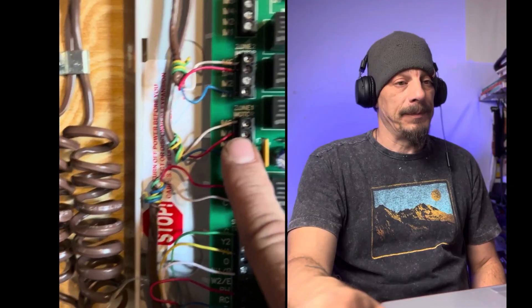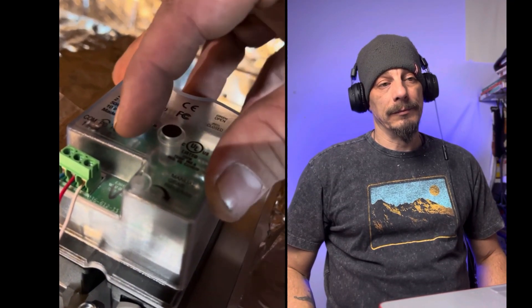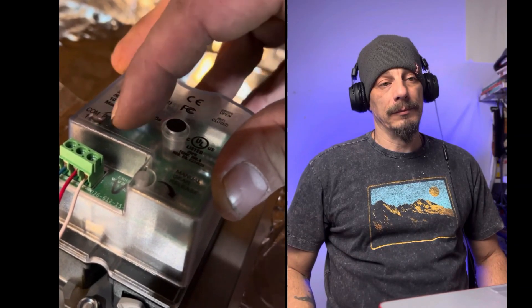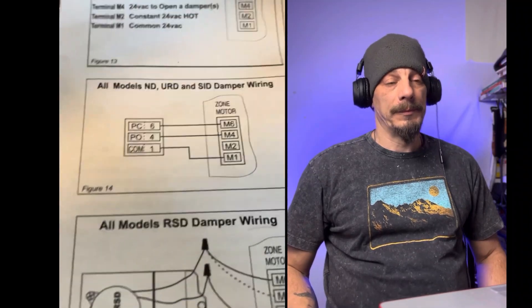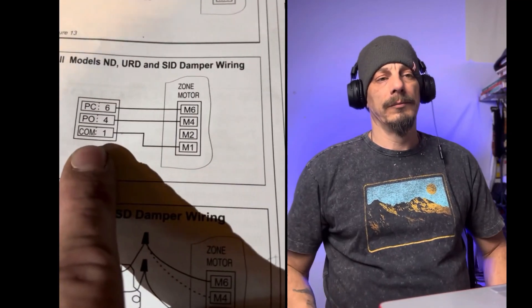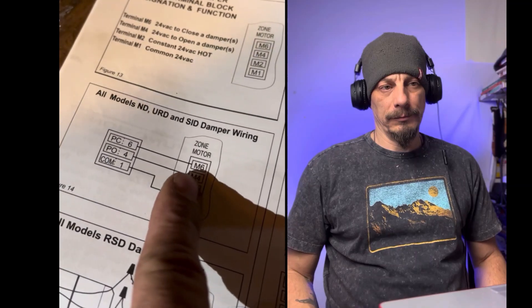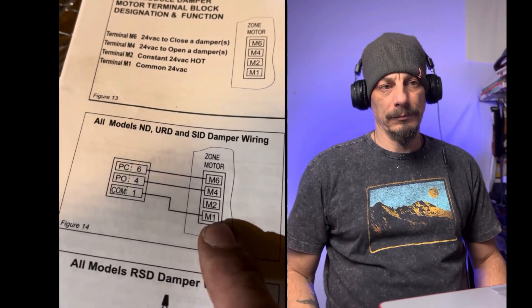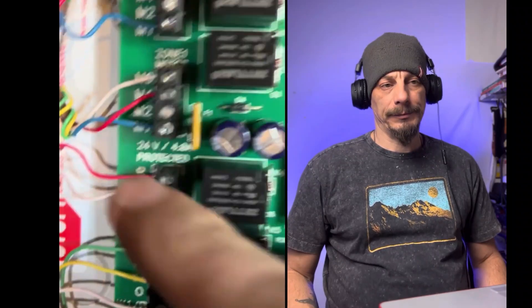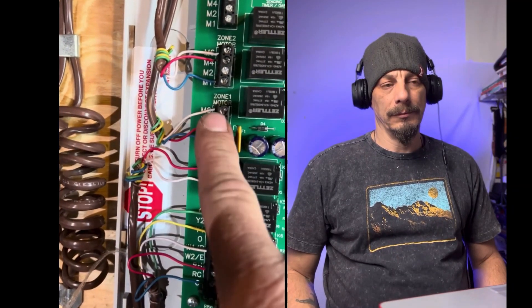Over here are the zone dampers. For this ND-type damper: terminal 1 is common (M1), terminal 4 is power open (M4), and terminal 6 is power closed (M6). This comes with the dampers - the manual shows you the wiring configuration for different damper types. For the ND damper shown here, M1 is common, M4 is power open, and M6 is power closed. We're not using M2 on this one.